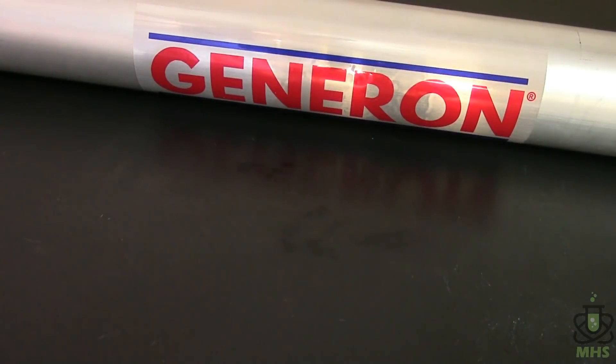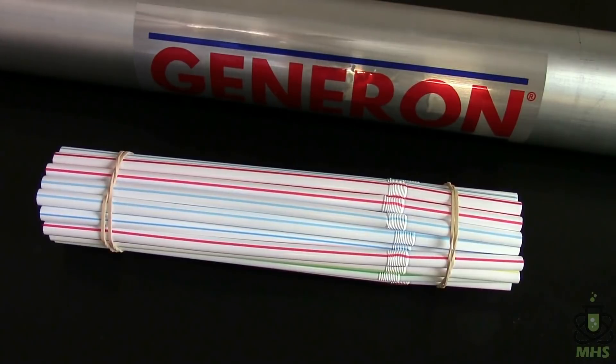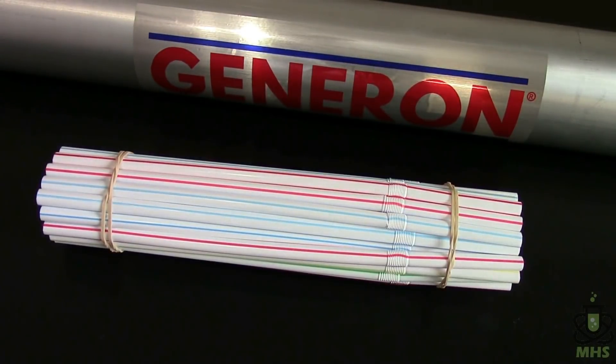The way it does this is the inside of the module is filled with a lot of tiny hollow fibers which you can visualize as a bundle of straws. Now the real fibers inside the module are really tiny. This one module has about 40,000 of them in there so that gives a huge surface area to maximize filtration efficiency.